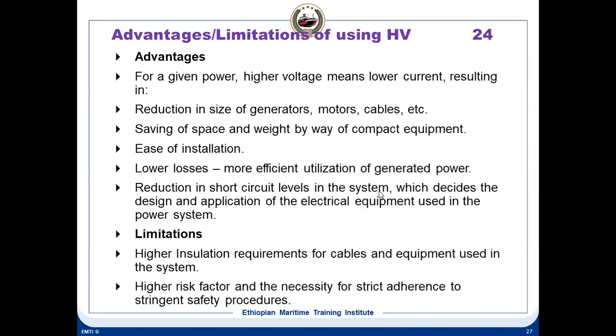Okay. And what are the limitations? What are the disadvantages? First is higher insulation requirements for cables and equipment used in the system. Your insulation requirements will become very high, because instead of 440, now you are sending, let's say, 11,000 volts or 6,600 volts. So the cable insulation has to be very thick. The current carrying conductor is the same, but the insulation becomes very thick. So higher insulation requirement is one of the disadvantages.